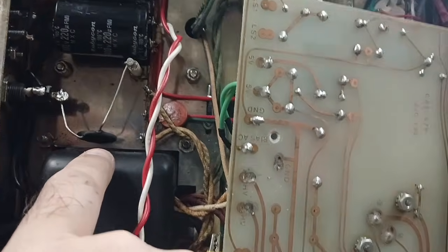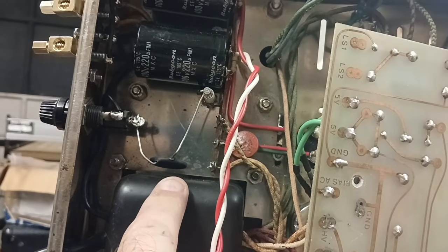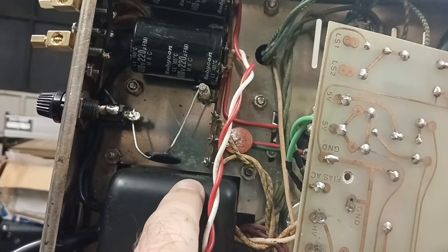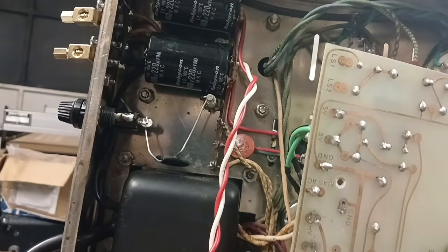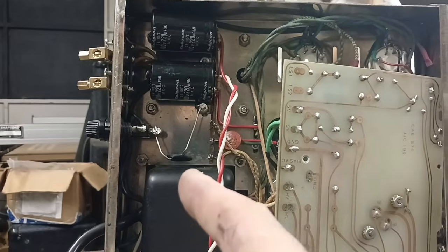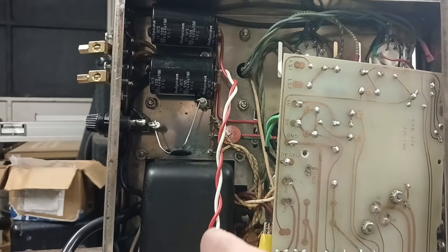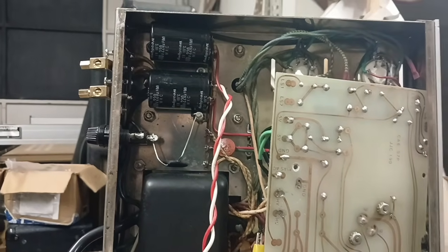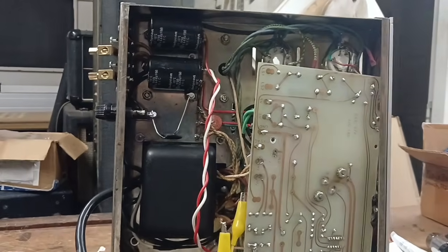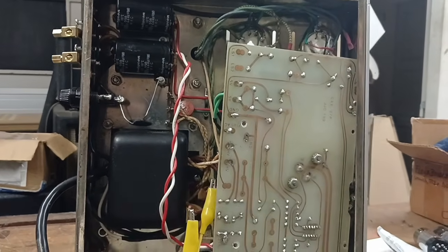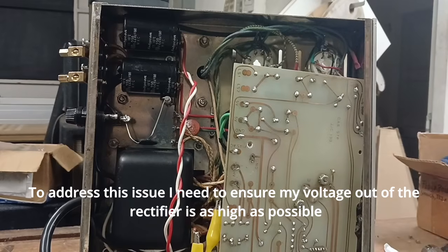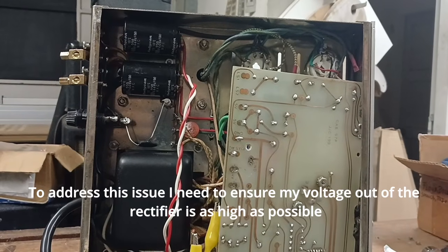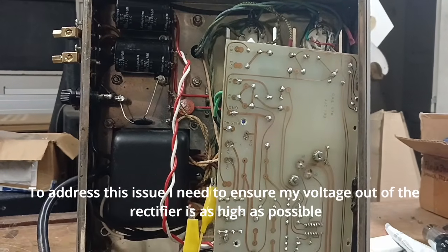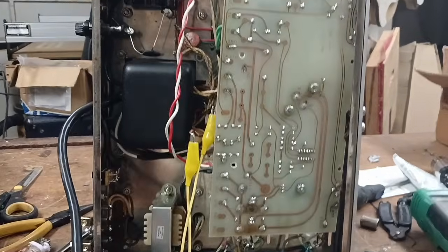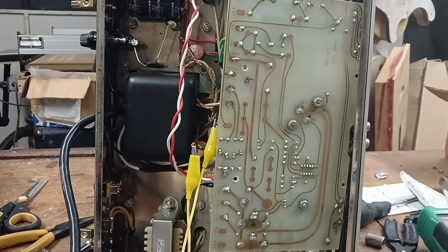Early on in the project, I put in this thermistor, which gives some resistance to the primary circuit before you even hit the transformer. As it heats up, it goes to low resistance and it's out of the circuit, and everything operates as it should. However, I never really tested whether this is in fact going low resistance, or if it's staying at a certain resistance and lowering our secondary voltages. I want to check the voltage, then bypass that thermistor and see what the voltage is.